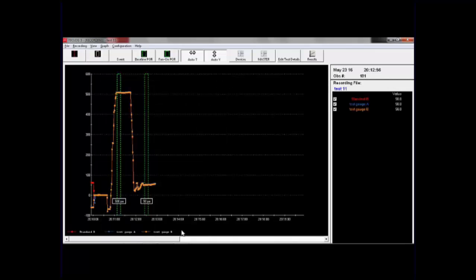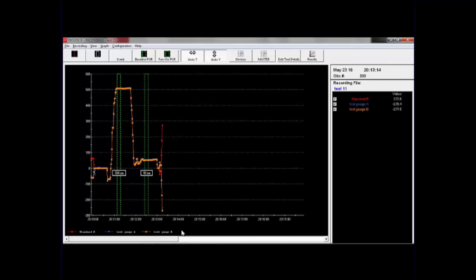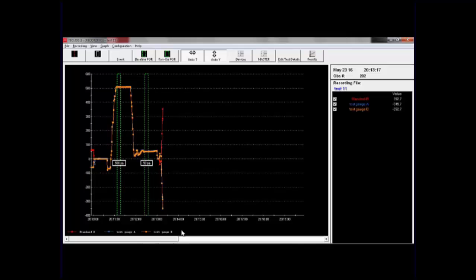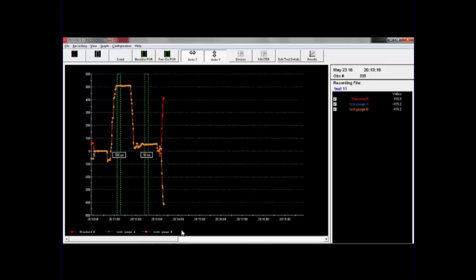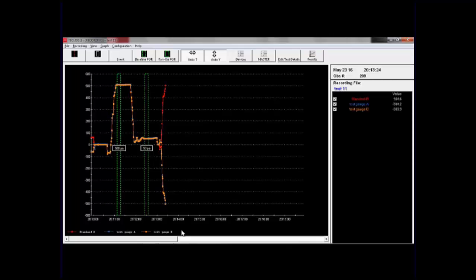Okay, and now I'm going to switch the tubes on the test gauge from reference to input. So switch those two from reference to input, and I'm going to pull out to get to, I didn't change my reference on the standard gauge, so I'm still looking for a positive 500 on that one, but it will be negative 500 on the other. We just need to be within 30 pascals.